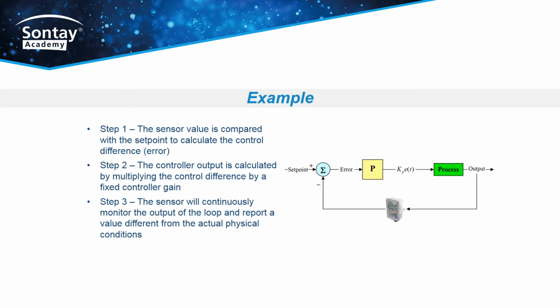Step 3. The sensor will continuously monitor the output of the loop and report a value different from the actual physical conditions. Whilst the system will ultimately come under control, the conditions will be consistently incorrect due to the inaccuracy of the sensor.